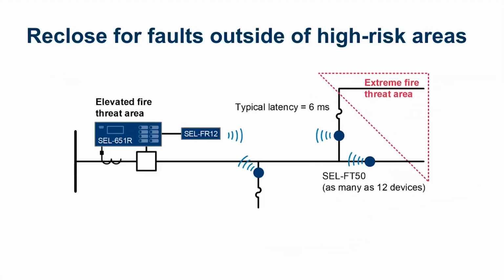So this figure does a good job of explaining what I need and why I need dynamic reclosing. Let's assume we have a 651R, which is protecting this feeder. I have a lateral right here, which is in an extreme fire threat area. And I have a second lateral here. Let's assume that this lateral is in an area where there are critical loads, like a hospital or maybe an airport. In that case, if I have a fault on this lateral, ideally I don't want to reclose. I want to lock out immediately. But if the fault is on this lateral, I want to reclose. So now I want to dynamically control the 651R to reclose in certain cases, but not reclose in the others.